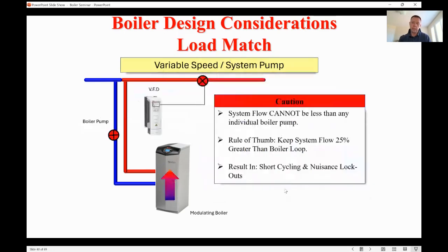But the other cool thing is that the controls in most of these boilers can act as an anticipator here. Most boilers these days can take an input from a VFD pump. So let's say you have a building here and, all of a sudden, it gets sunny. Part of that building gets sunny, gets hot. Well, the zones close up, the VFD starts backing down. It'll send a signal to that boiler saying, hey, there's less load on the system. That doesn't affect the set point because the indoor-outdoor reset determines the set point. If it's 150 degrees, it's 150 degrees, but there's less load out there.